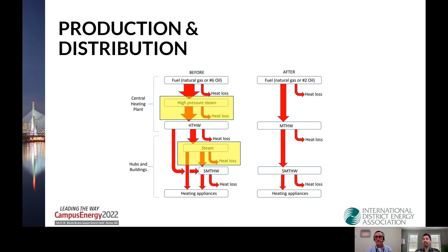So this is the distribution high temperature loop for Brown University's campus. For those who don't know, high temperature hot water is basically water at 350 degrees Fahrenheit that is kept under pressure and distributed underground all over the building, so you can produce either hot water or high pressure steam. So it's a very complex system.